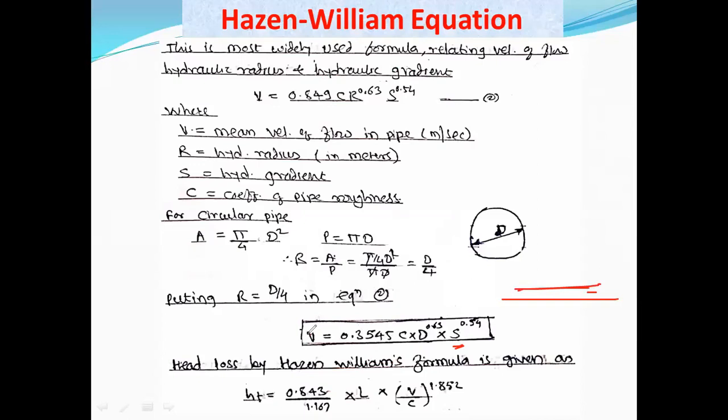These equations. Generally, the velocity of flow inside the pipe will be 1.2 meter per second. We put this standard value here, and then we find at which slope this pipeline has to be laid so that it will have this velocity of 1.2 meter per second. If that slope is not maintained, then this velocity will not be achieved. Okay. So depending upon the characteristics of the pipe surface, this value of the velocity will vary. If the roughness is more, then the velocity value may change there.